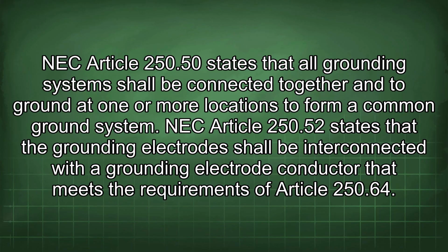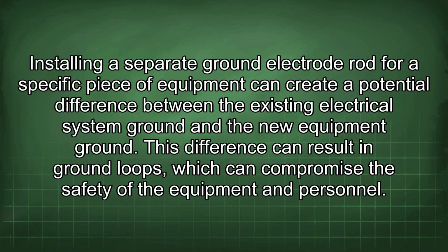NEC Article 250.50 states that all grounding systems shall be connected together and to ground at one or more locations to form a common ground system. NEC Article 250.52 states that the grounding electrode shall be interconnected with a grounding electrode conductor that meets the requirements of Article 250.64. Installing a separate ground electrode rod for a specific piece of equipment can create a potential difference between the existing electrical system ground and the new equipment ground.